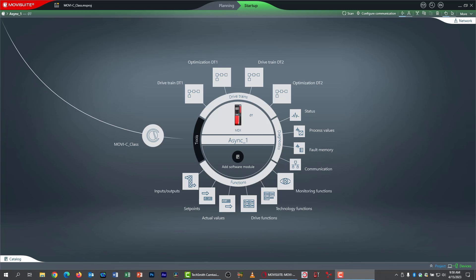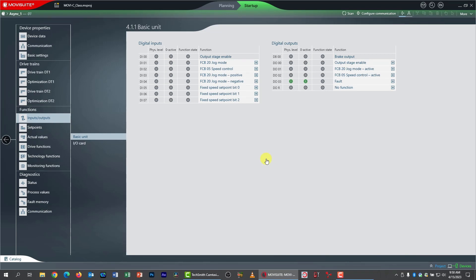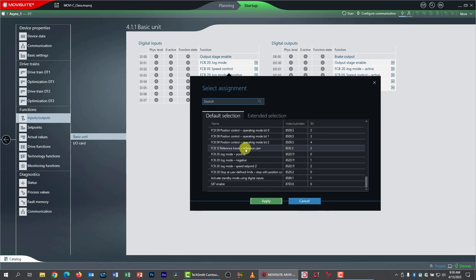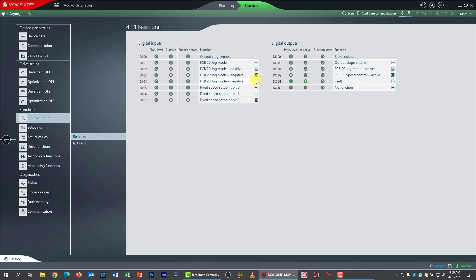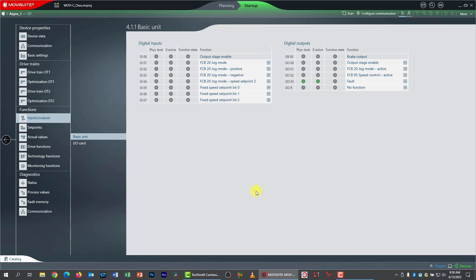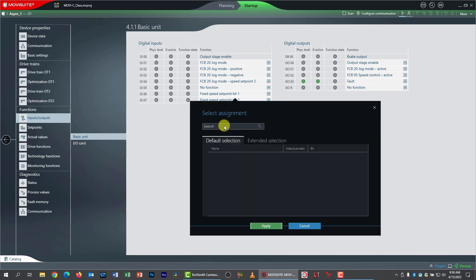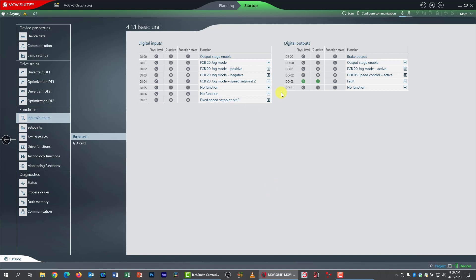First, we need to configure the drive to allow us to play with ramps. We're going to play with jogging ramps first, so we need to reassign some IO signals. I'll click the inputs and outputs shortcut and make the changes the instructions specify. I've set up jog mode: DI01 activates the FCB, DI02 and DI03 control the direction, and DI04 controls the two jog speeds.